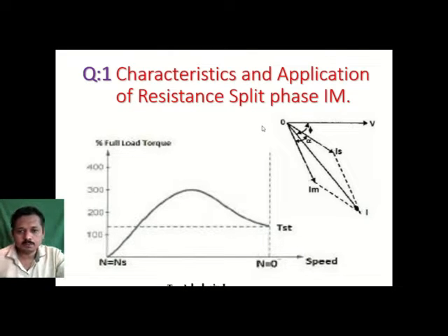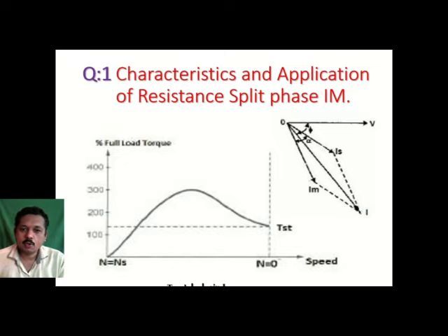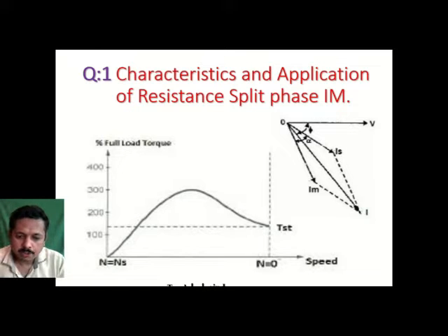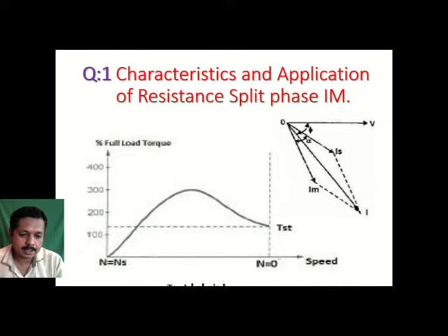Because of the fine winding in the main winding, we get a good starting torque in the resistance split phase motor. This motor doesn't need any special components, making it available at very low cost and popular in the industry. However, this motor has a limitation: the starting time must be less than 5 seconds, otherwise the starting winding can be damaged. The very fine current-carrying winding draws very high current, causing high copper loss, high temperature rise, and possible winding damage. Using a thermal relay provides safety protection.